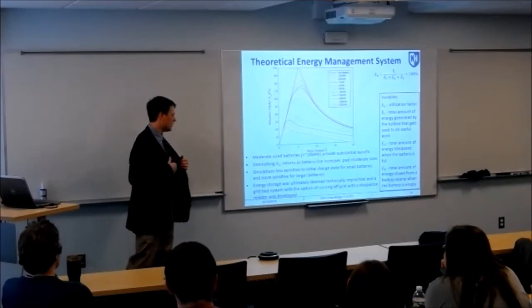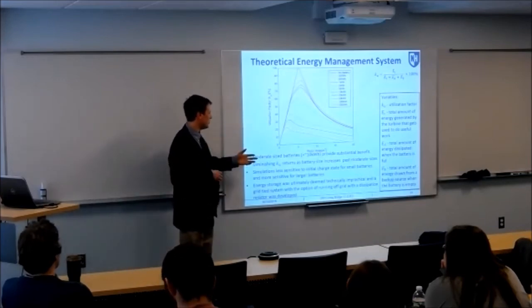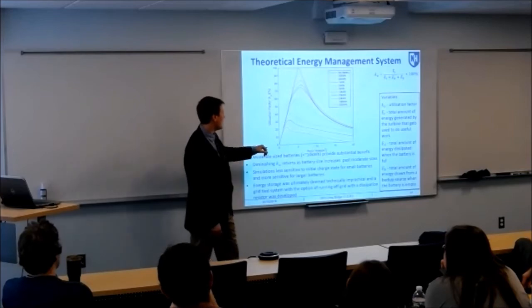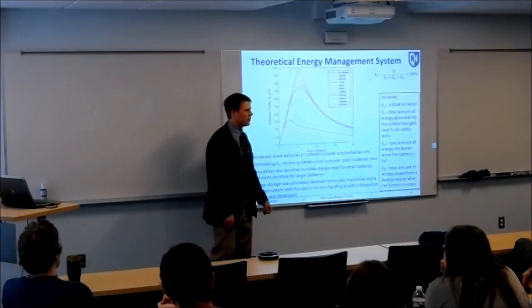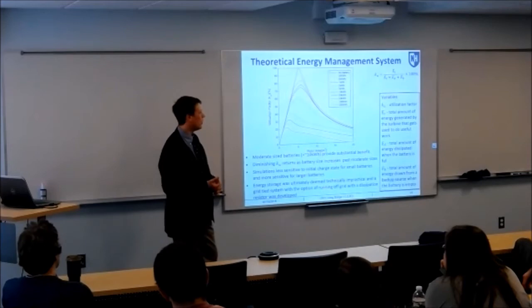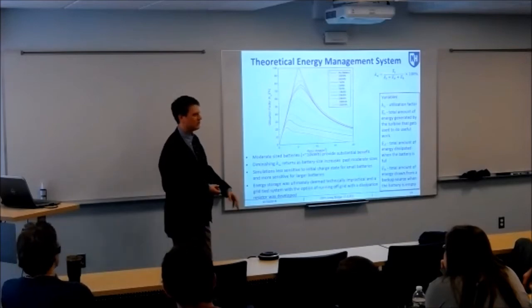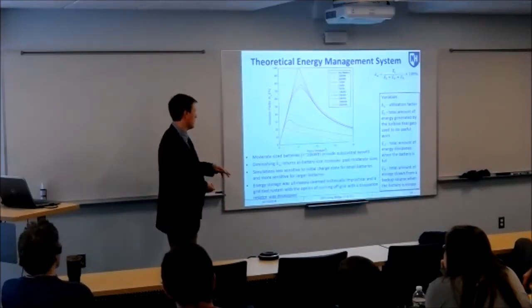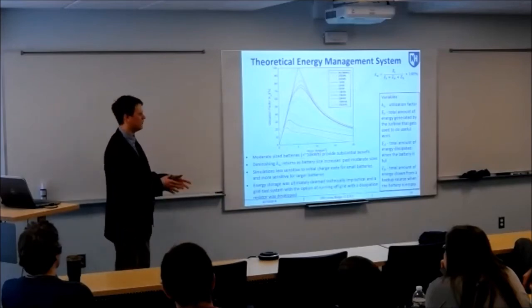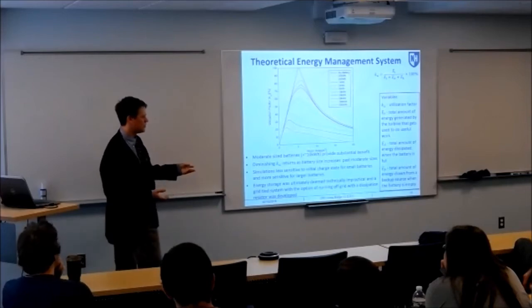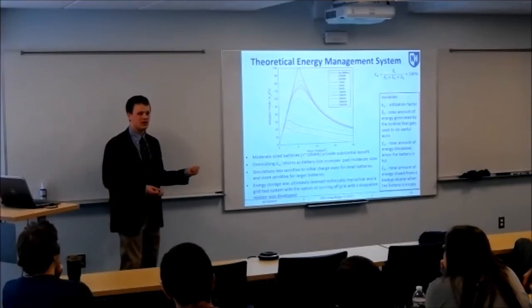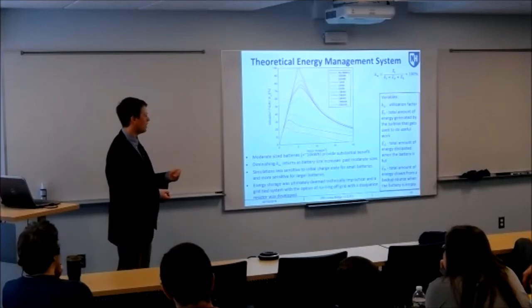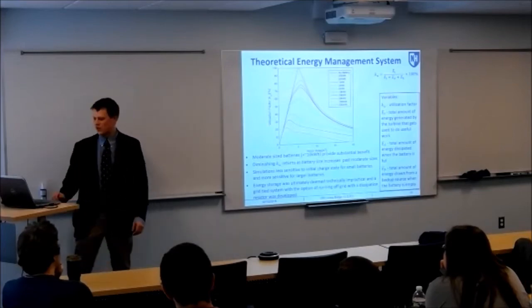Ultimately, this system was deemed infeasible because we would need a ridiculously large battery to utilize all of the energy produced, and some of the components needed to implement a system like this aren't readily available off the shelf. It wasn't an area of the project where we wanted to focus our efforts to deploy this system, so we ended up selecting a grid-tied net metered system where we would always have a utilization factor of 100.